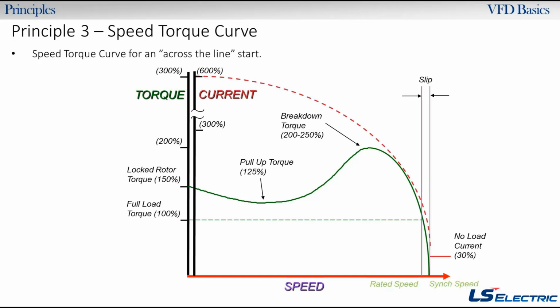So something that'd be important to understand is this right here, which is a speed torque curve. Now this speed torque curve is for an across the line start. And if you guys remember what across the line means, that means we're just running a contactor from the power supply to the motor. Contactor closes, motor kicks off within a fraction of a second. So this whole curve right here is actually time over a fraction of a second.